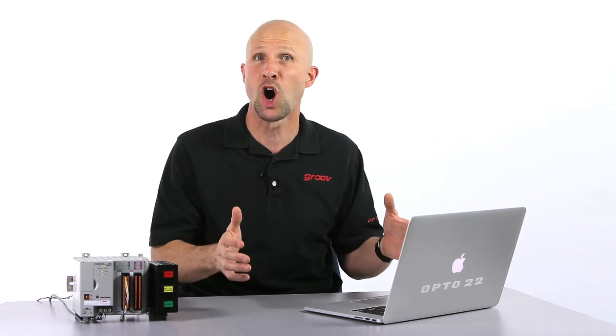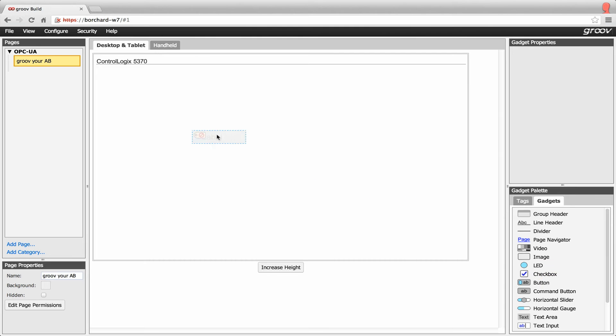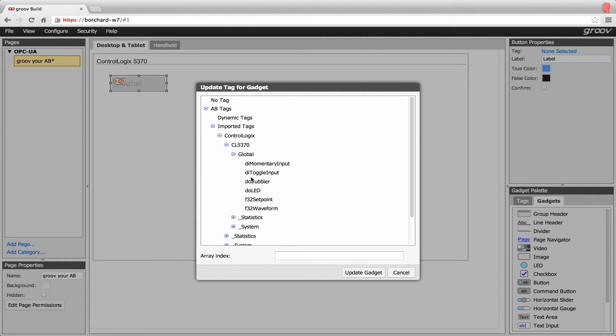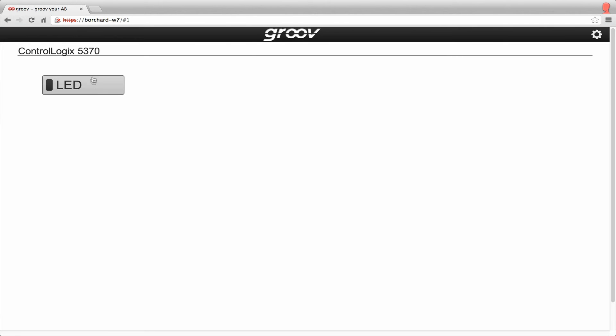Now the last step is the really fun part — building our page in Groove with no programming. Click on the button gadget from the gadget palette and drag that over. Select the AB tags, then imported tags, then ControlLogix, then the device, then global. There's our digital point — click it and then click update gadget. I'm going to call it LED and change the color to red. Let's try it out. Click on file, save all changes, and switch to Groove view. If there's a button, I just have to click it. Yep, it works a ripper.